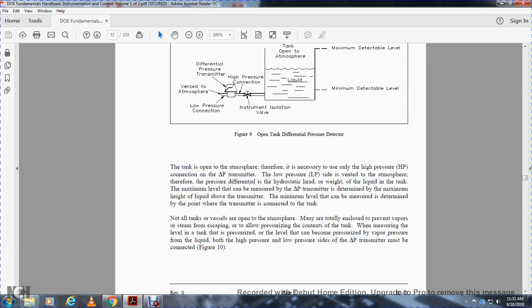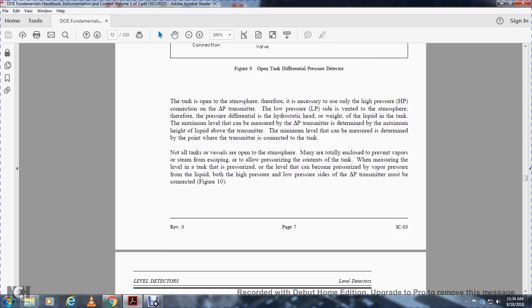Not all tanks and vessels are open to the atmosphere. Many are totally enclosed, with vapor present. The escaping steam can cause pressurization of the tank contents when measuring the level of a pressurized tank, so the level reading becomes affected by the vapor pressure of the liquid. Both the high pressure and low pressure sides of the differential pressure transmitter must be connected, as in Figure 10.